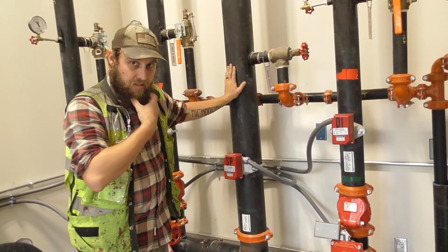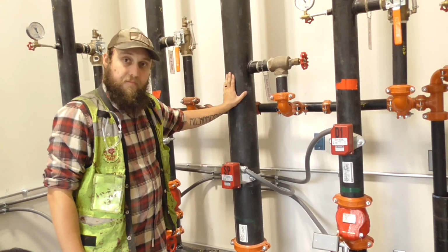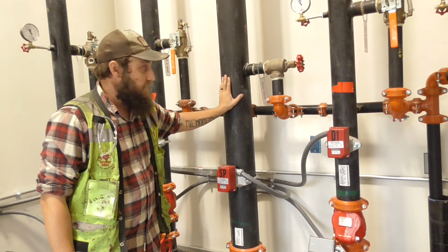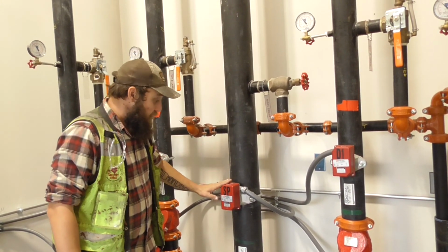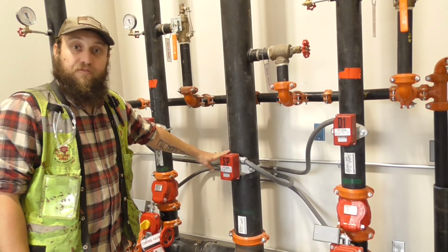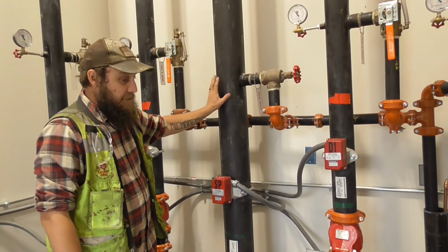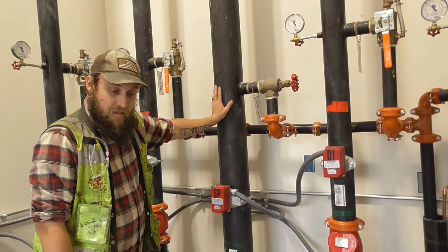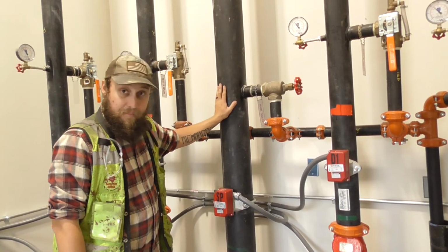This is also the system which the fire department will pull water from for their fire hoses throughout the building. Anytime anyone opens any of those valves, a flow switch here will indicate water flow and will set the general fire alarm off. This feeds every stairwell as well as multiple roof locations. That's your standpipe system here.